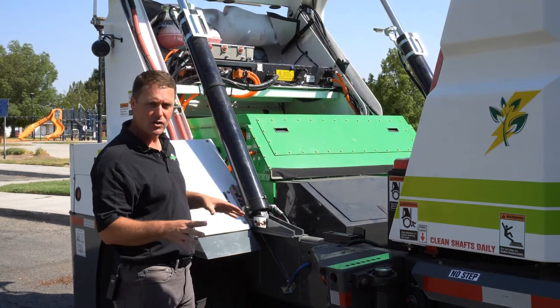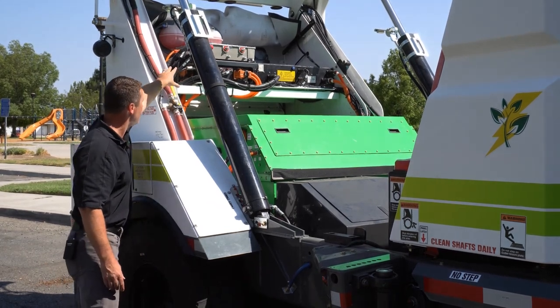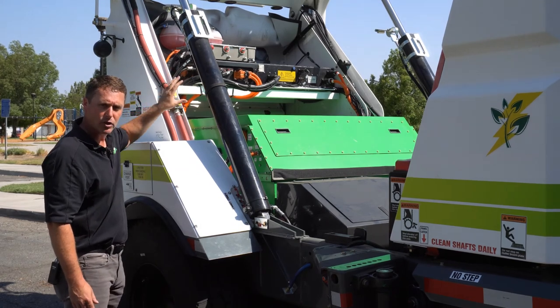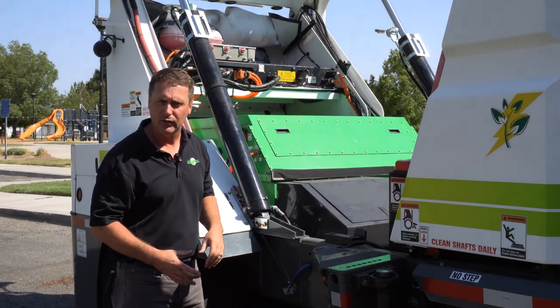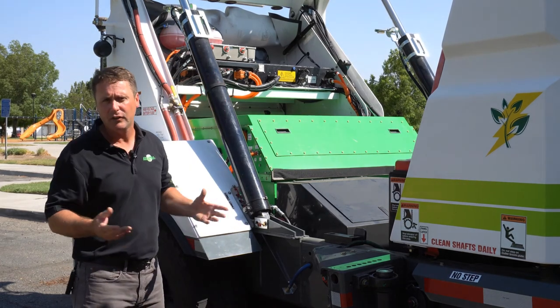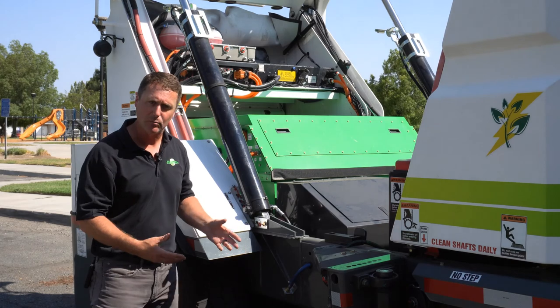The system is actually set up with an onboard charger. So if I look at the component up to the top, the box up to the top that says 13.8 volts, that's a 20 kilowatt charger. As far as the charge system goes, we are actually charging the machine using a standard level 2 J1772 charge pack. Ultimately what you need in your facility is going to be 240 volts at 50 amps, as long as we can plug into that.